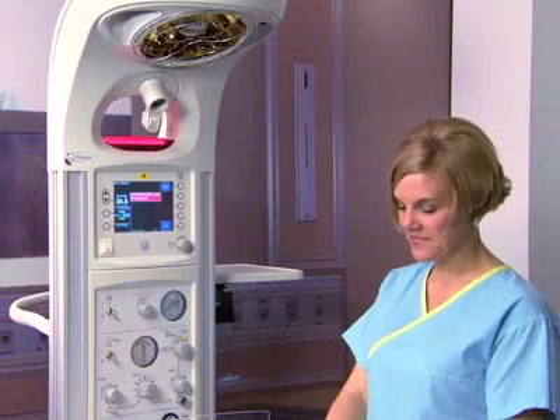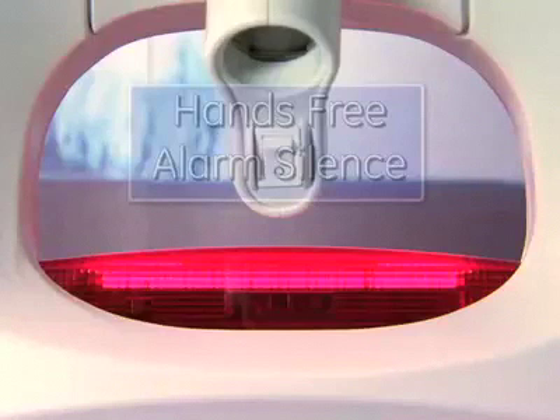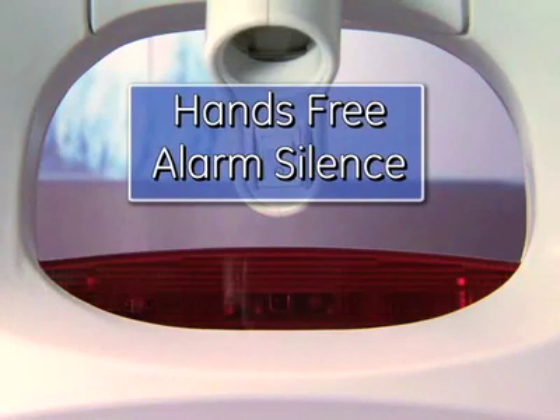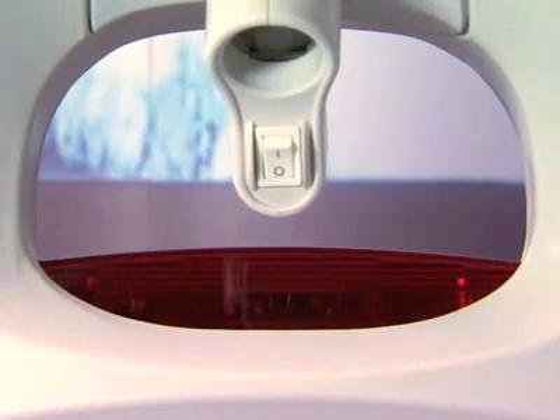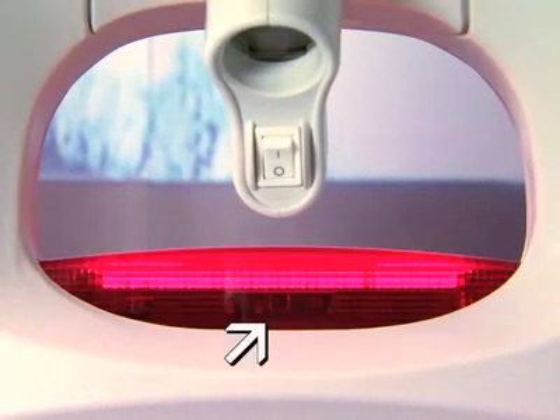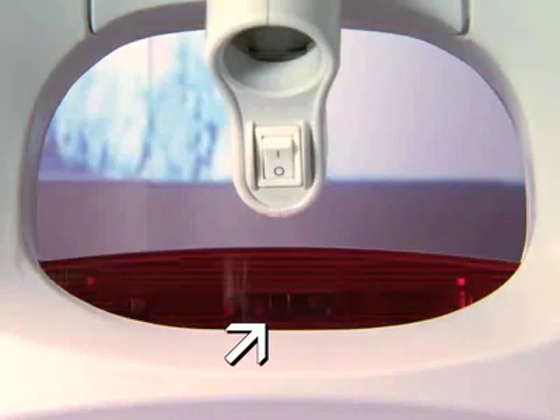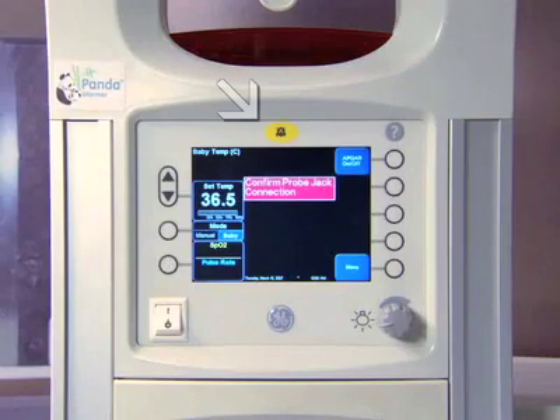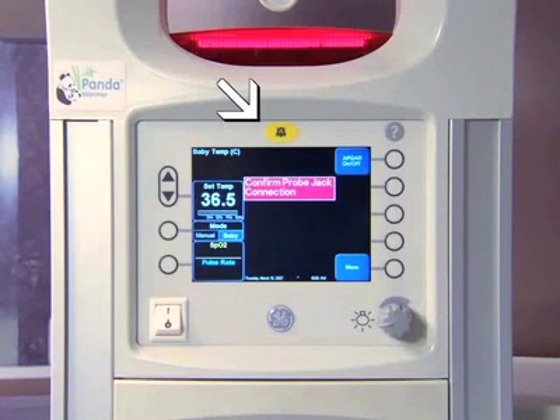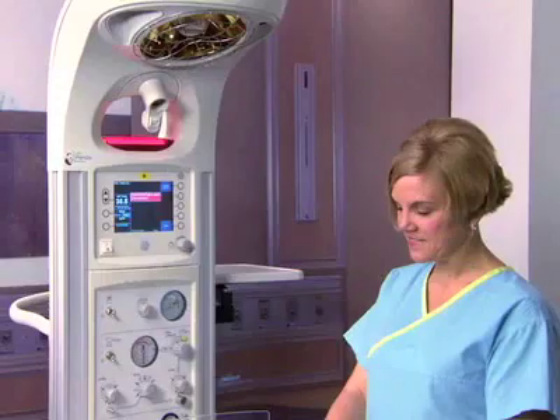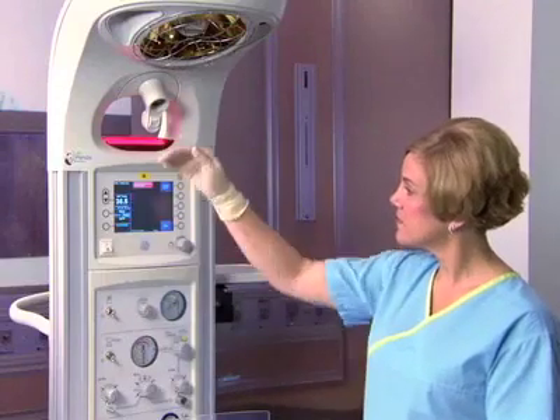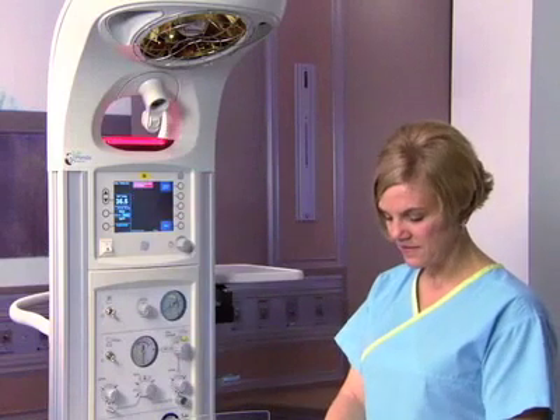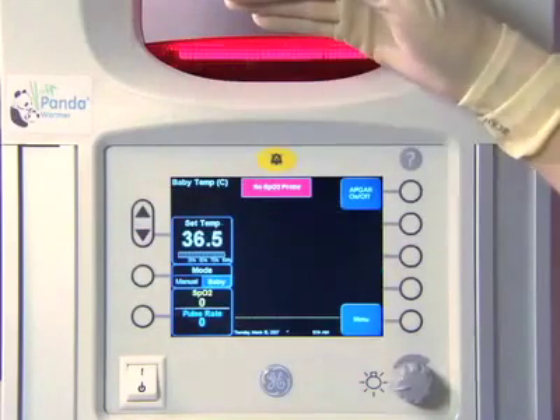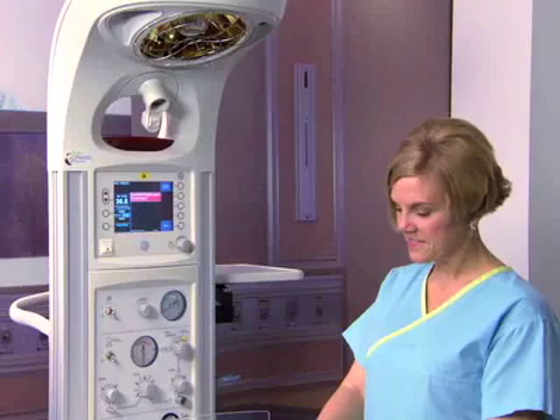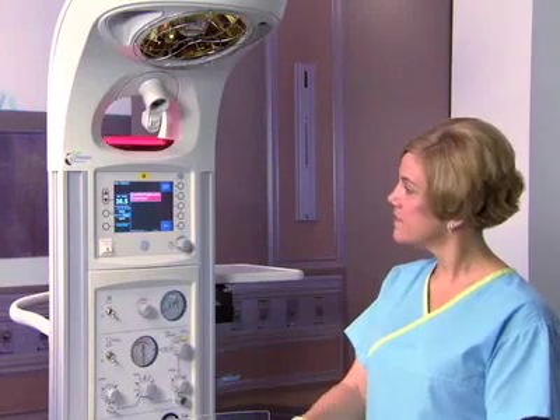Your PandaWarmer has a new way to silence alarms. We call it hands-free alarm silence. The motion sensor for the hands-free alarm silence is located in the alarm light panel. Silencing an alarm with the hands-free alarm silence works exactly the same as pressing the alarm silence key for all alarms. Silence the alarm by gently waving your hand approximately 2 to 6 inches in front of the sensor. Using the hands-free alarm silence will allow you to silence alarms without touching a surface during a procedure or intervention.